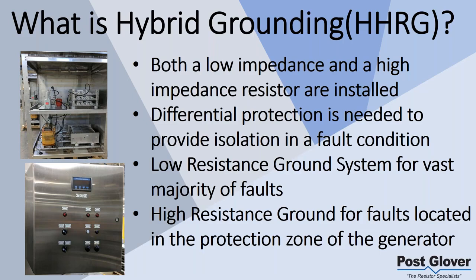So the general idea is you're going to have a low resistance ground system for the vast majority of your faults. However, for the faults that are located in the generator area, stator faults, etc., you're going to be high resistance grounded, and we'll go into what that looks like.